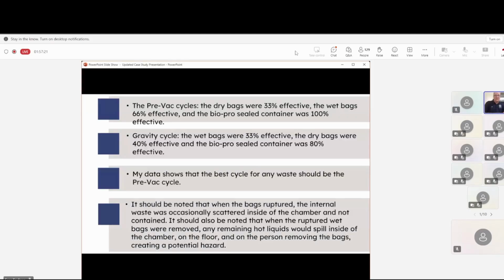And then the pre-vac cycle here is, hang on, something in my way. Pre-vac cycles, the dry bags were 33% effective. The wet bags were 66% effective. And the BioPro was 100% on the pre-vac. That 33 to 66%, that is Russian roulette. And again, that's only 5%. I only had 2 bags in that BioPro in that autoclave. It didn't take up much room.